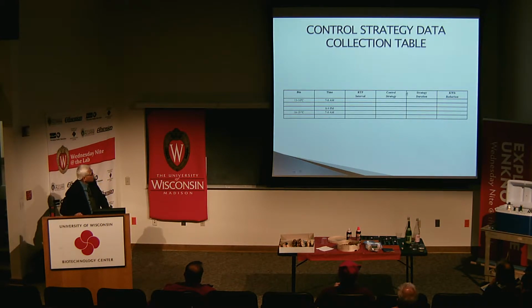Then we have what type of control strategy it is. Is it supply air reset? Is it chilled water reset? Is it floating control? Is it optimal stop? Is it optimal start? So each of those control strategies is evaluated from the commissioning process.